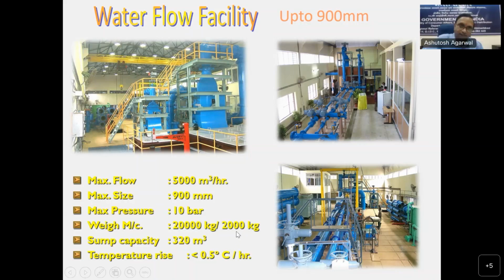Here, the weighing machines are selected in such a way that you get maximum accuracy for the collection. If your flow rate is very low, then you go for 2000 kg, and they also have a weighing machine of 300 kg and lesser if the flow rate is very low. Micro flow meters, very low flow rate meters, are also calibrated here, using weighing machines of the order of 2 kg or maybe 500 grams. They have different kinds of weighing machines used for lower flow rates.